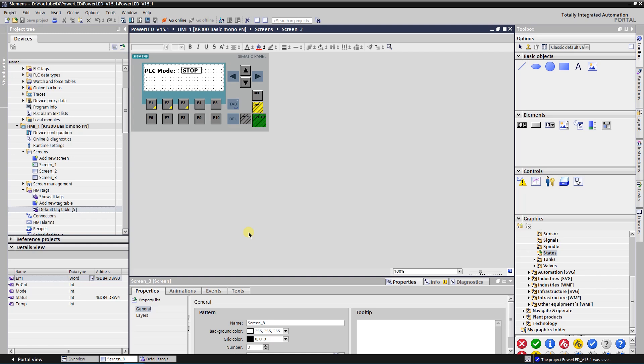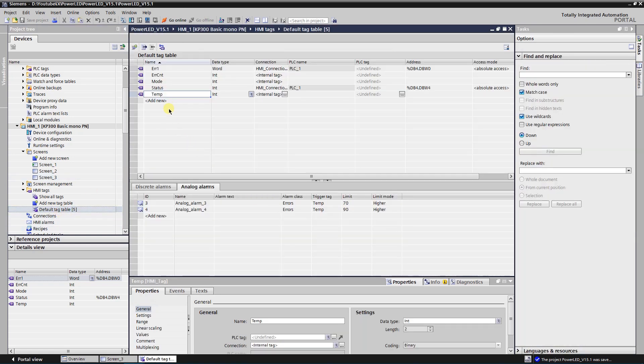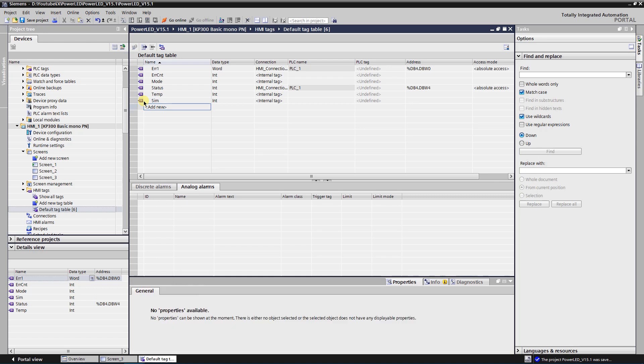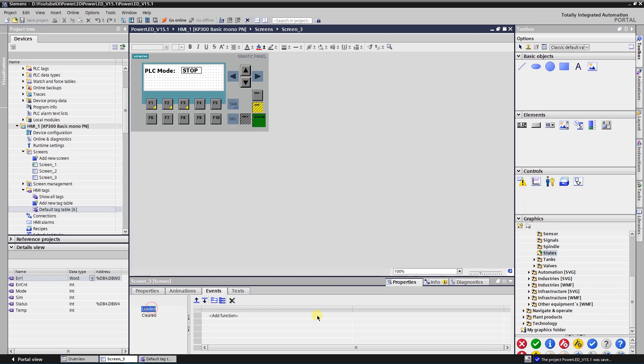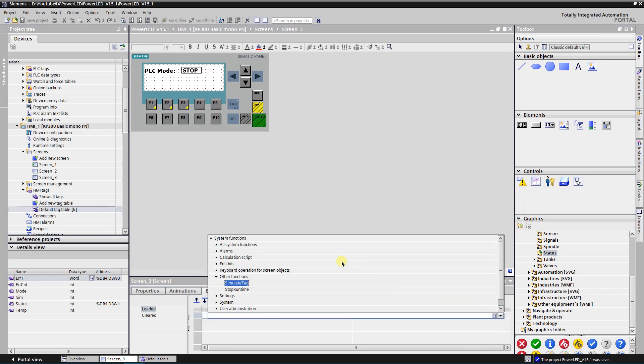Let's upgrade our application even more. This time I will add functionality that checks the PLC mode at regular intervals. For that purpose I will use a function called Simulate Tag. This function can be accessed in the events of the screen. Create an integer type tag, as this function accepts only tags of type integer. Switch to your screen and then switch to the screen events. Select event Loaded and find the function Simulate Tag under System Functions, Other Functions.